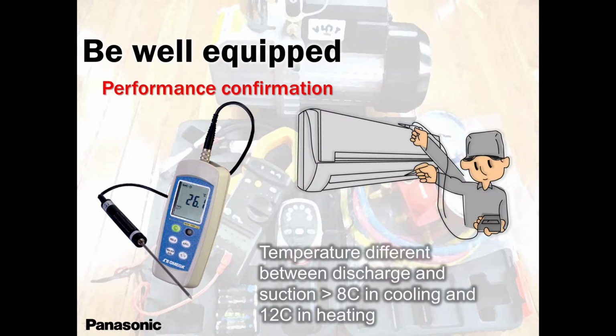When you have a mechanical problem, that's where you will do this delta T test, you know. And most of the time, 13 to 15 degrees Fahrenheit in cooling and around 25 degrees Fahrenheit in heating is more than acceptable for around 15 to 20 minutes to 30 minutes of operation. So always remember, it's a good idea to have that. Now delta T will vary depending on the fan speed. If the fan speed is low, then it could be a problem. If the fan speed is too high, it could be a problem. So at a moderate fan speed, you should expect 13 to 15 degrees Fahrenheit in cooling, 25 degrees in heating.